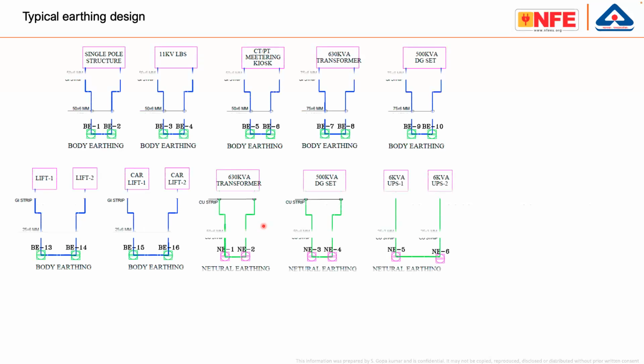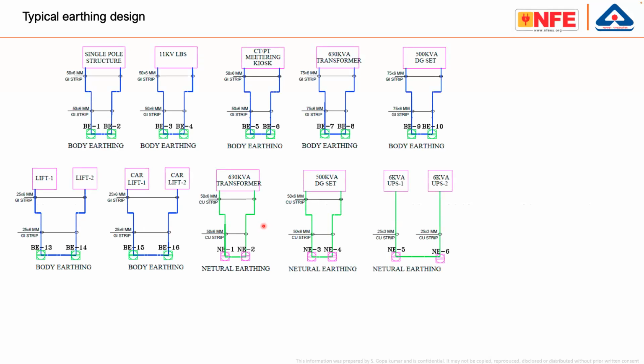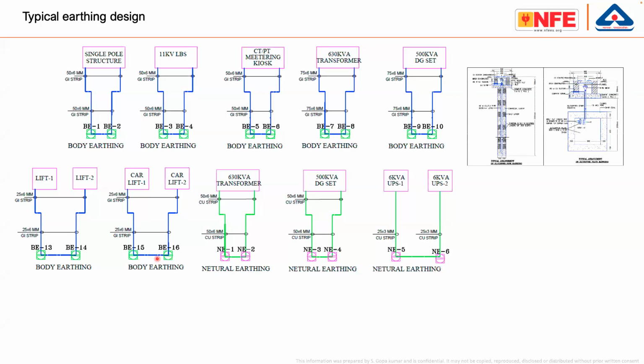Now, if you look at the typical earthing connections made in our country, you can see here a drawing which I received 2 days back for checking. You can see the transformer having neutral separate, body separate; the DG having neutral separate, body separate, two numbers. Then lift 1 and 2, for example, body earthing separate, then lift car separate. Everywhere, these electrical appliances are connected to separate earth electrodes in soil, probably a pipe or chemical or plate electrode or whatever it is.